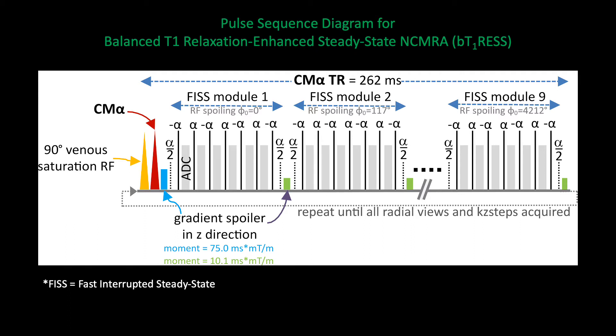The BTRESS sequence for non-contrast MR angiography relies on the use of a Fast Interrupted Steady-State, or FISS, readout. There are two main reasons for using this instead of a traditional balanced Steady-State free precession readout. One is that FISS provides natural fat suppression, which is otherwise difficult to obtain when using a continuous radial acquisition as is the case with bT1RESS. In addition, FISS is much less sensitive to flow artifacts than a traditional balanced Steady-State free precession acquisition.